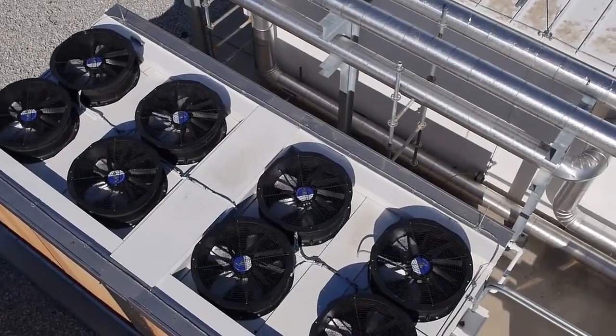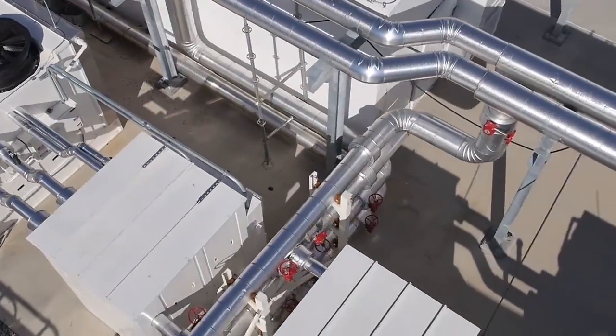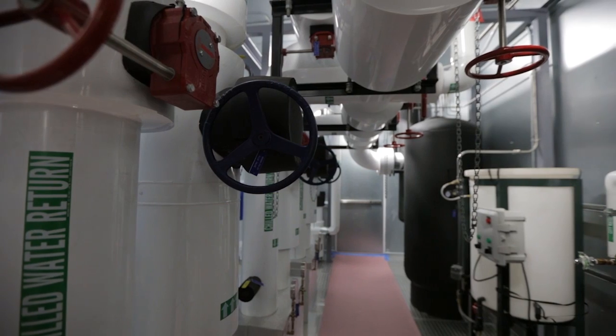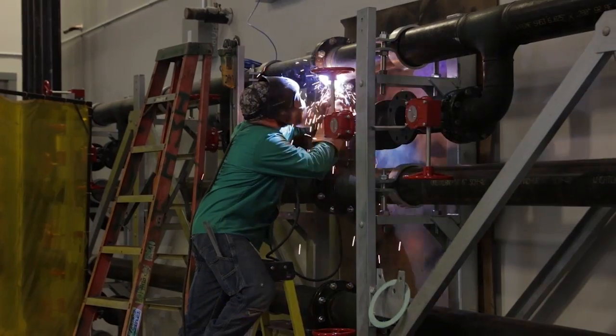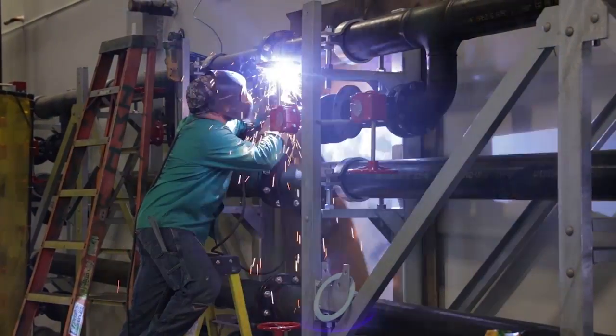All of the equipment we deploy on our sites is tied into our Energy Metrics platform, giving constant feedback on the operation of that equipment and how it reacts in the particular site we're operating in. The difference between that delivery model and a traditional data center model is that a traditional model installs equipment based on whatever is available for that environment, through a 3-bid process, whatever chiller or generator is the low bid ends up in your data center. They're not necessarily connected to a feedback loop back to the factory to figure out what works on the system, where they can improve, and how to optimize and deliver better systems going forward.